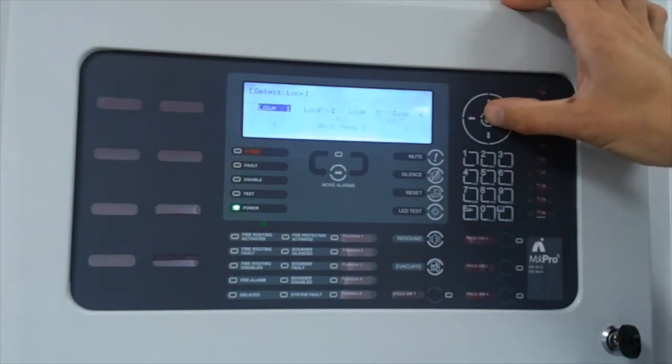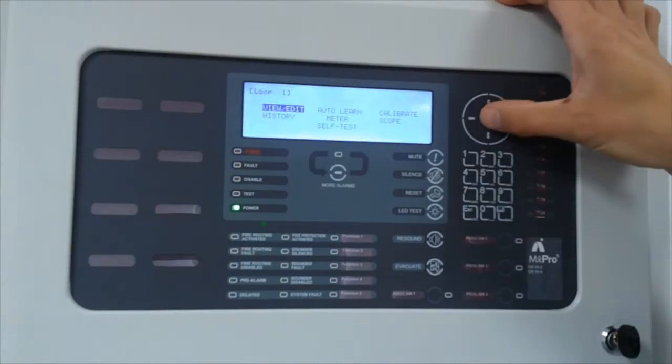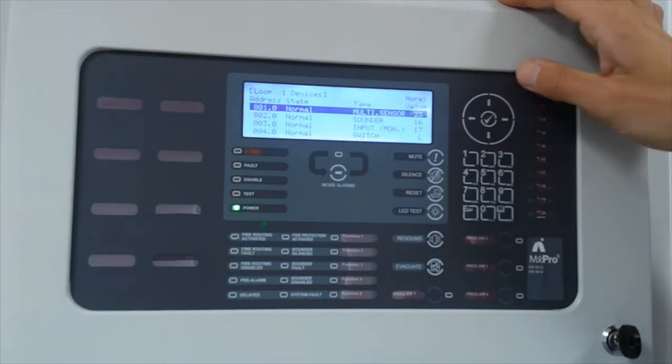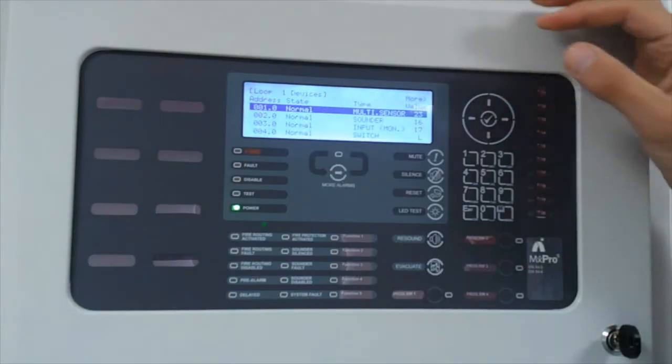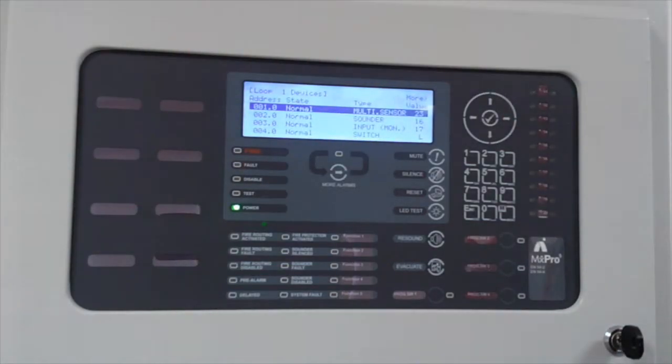We know it's on loop one. We go to the loops, loop one, identify your devices, making sure you've got the relevant information. One of the key points now is basic fault finding techniques. Put the panel into commissioning. Remember, the panel only drives in one direction - that's from the V out.